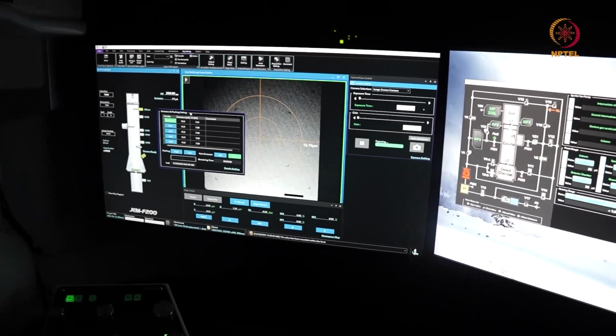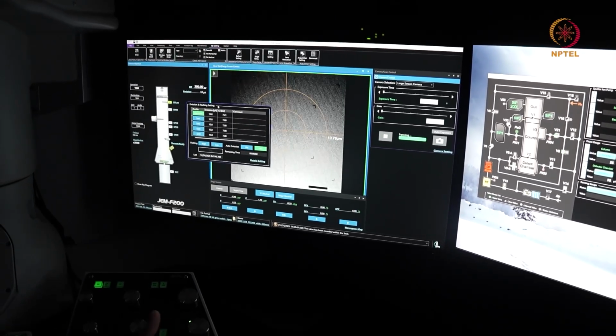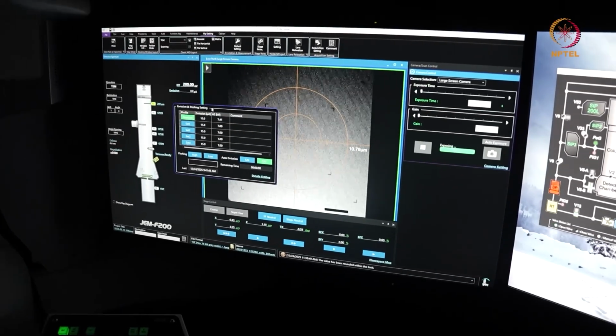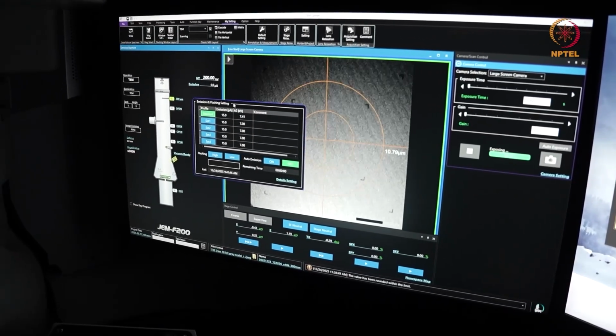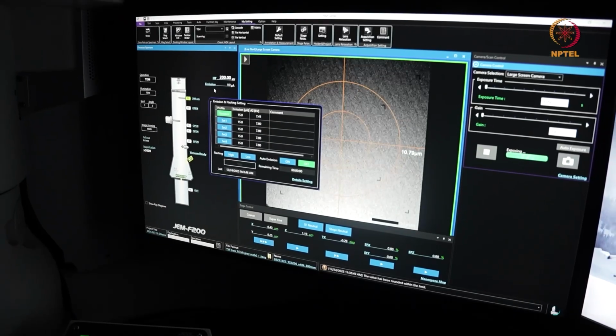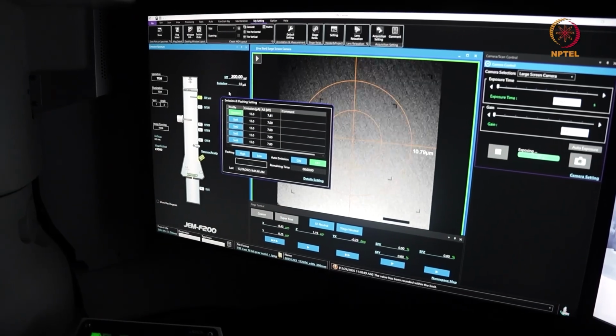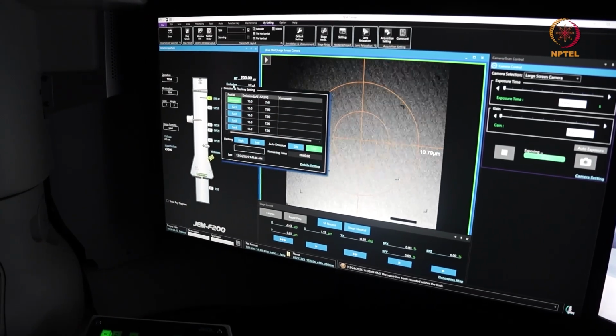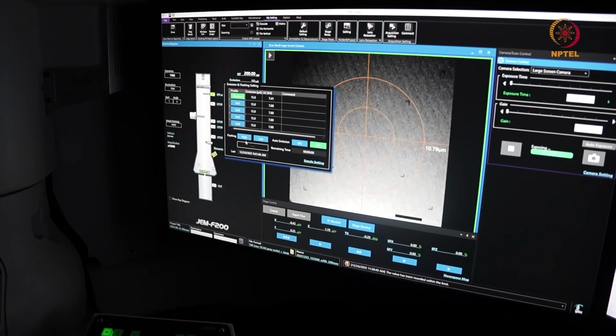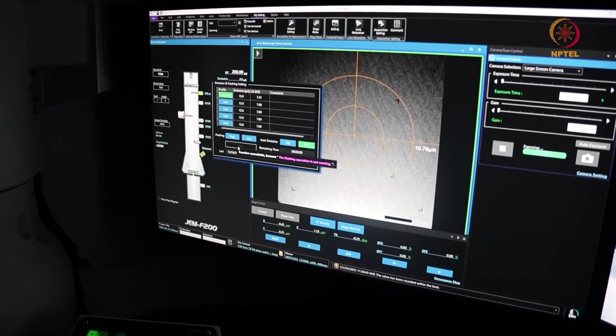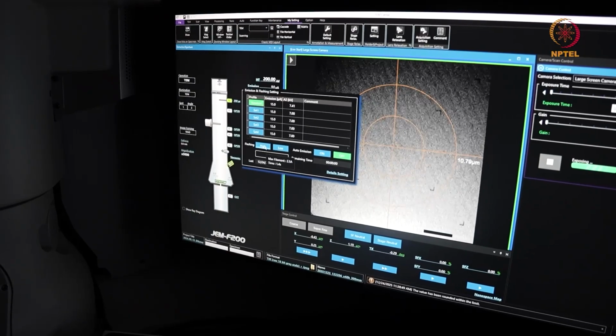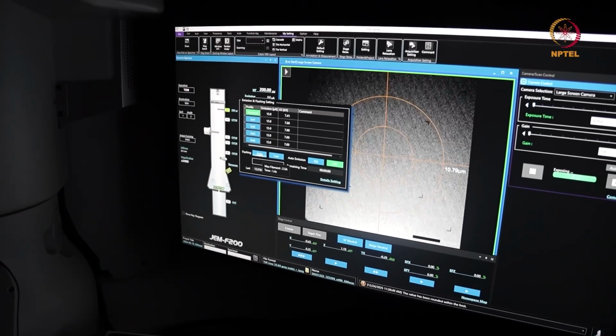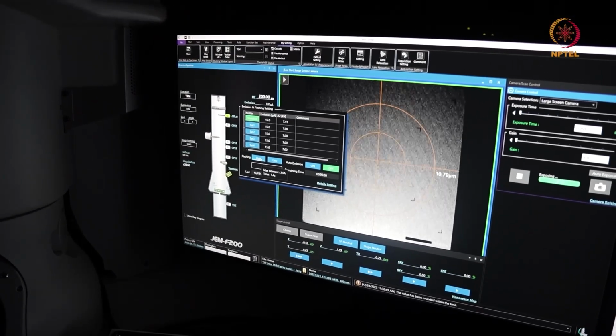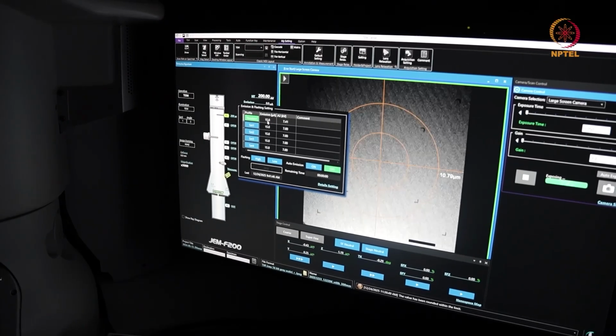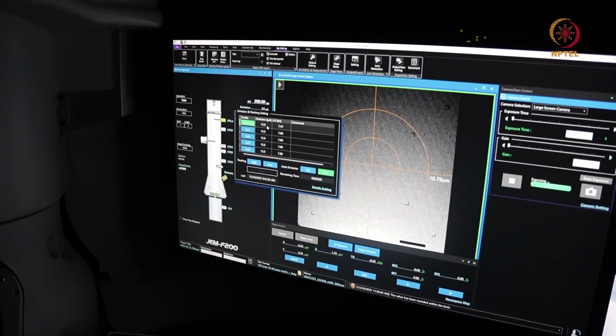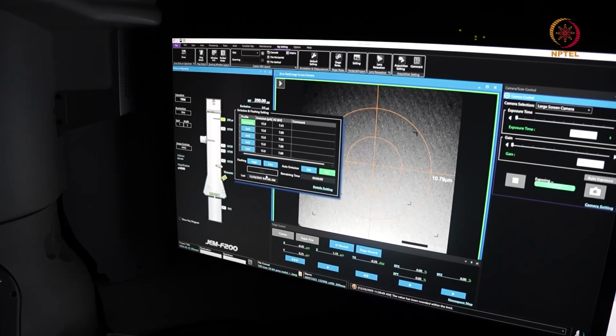So on the Cold FEG TEM, whether you're looking at the NEOARM F200 or the JEM F200, what you have is this interface, where if I right click on this particular window, this will remain stable here. The first thing that you do in the morning, if you have not done it already, is you start with a high flash. This is to ensure that your emission currents reach the preset value. In this particular instrument, the preset emission current value is around 15 microampere, and we've already flashed it once.